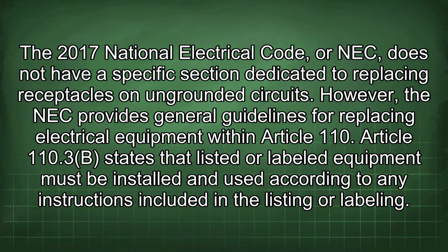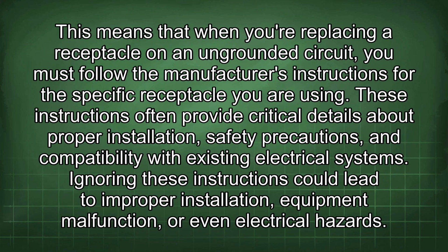The 2017 National Electrical Code, or NEC, does not have a specific section dedicated to replacing receptacles on ungrounded circuits. However, the NEC provides general guidelines for replacing electrical equipment within Article 110. Article 110.3(B) states that listed or labeled equipment must be installed and used according to any instructions included in the listing or labeling. This means that when you're replacing a receptacle on an ungrounded circuit, you must follow the manufacturer's instructions for the specific receptacle you are using.